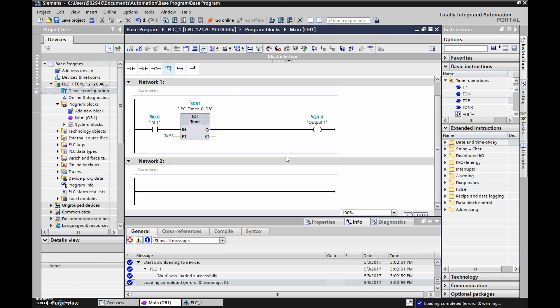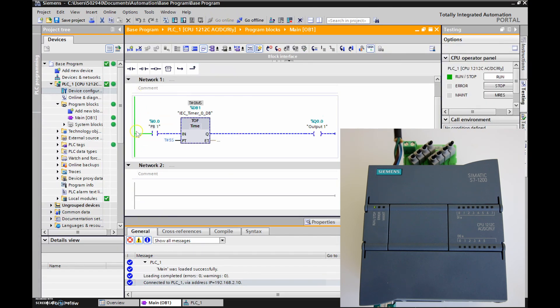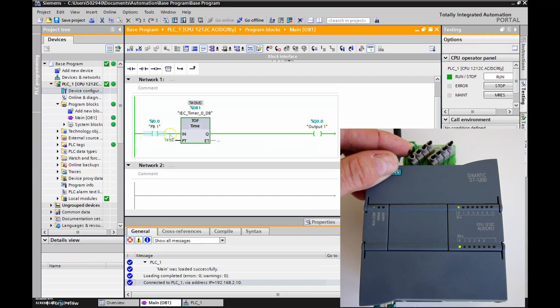We can go straight to monitoring — it turns online right away. Again the input goes into the timer with a preset of five seconds. When we close this switch on an off-delay timer, the output fires on immediately. So we close the switch and the output fires on right away. Now we're going to open the switch — that makes the input go false. An off-delay timer turns on, then when the input goes off it takes some time to revert to its rest state. So we take away logic continuity at Input 0 and the output stays on for five seconds.